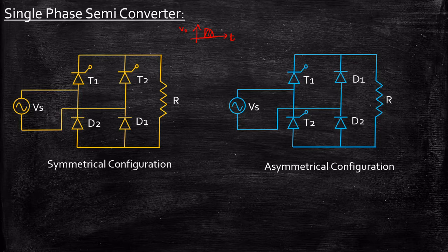Compared to a fully controlled rectifier circuit, we are replacing two SCRs with uncontrolled diodes D1 and D2. That's the major difference in terms of circuit, and the output voltage will always remain positive. You might ask why not use a fully controlled rectifier. The reason is SCRs are more expensive compared to a diode. So having four SCRs to get only positive output voltage makes no sense. We can replace two SCRs with a diode and still get the positive output voltage required at the load terminals. Hence, we use semi-converters in applications that demand only one quadrant operation.